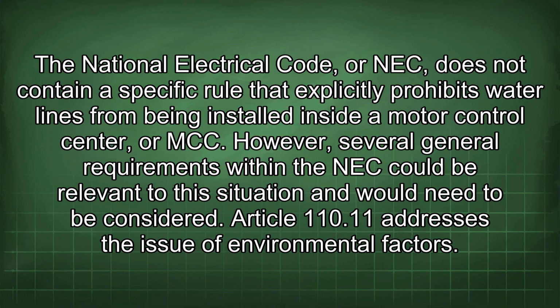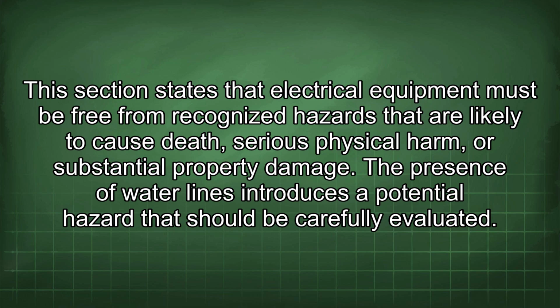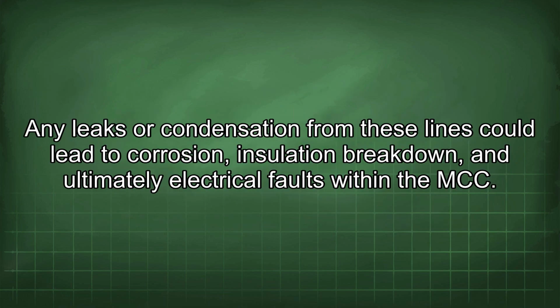Article 110.11 addresses the issue of environmental factors. This section states that electrical equipment must be free from recognized hazards that are likely to cause death, serious physical harm, or substantial property damage. The presence of water lines introduces a potential hazard that should be carefully evaluated. Any leaks or condensation from these lines could lead to corrosion, insulation breakdown, and ultimately electrical faults within the MCC.